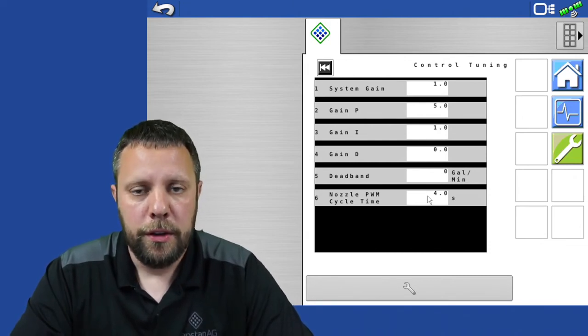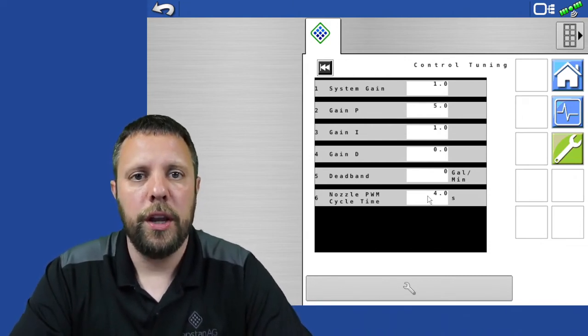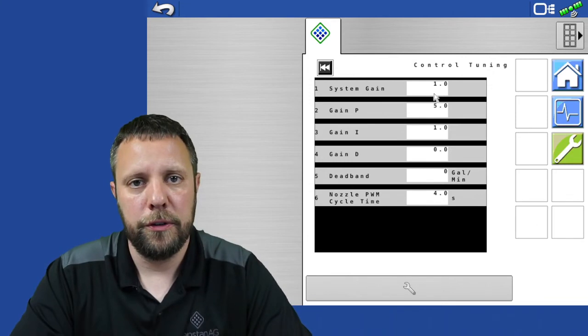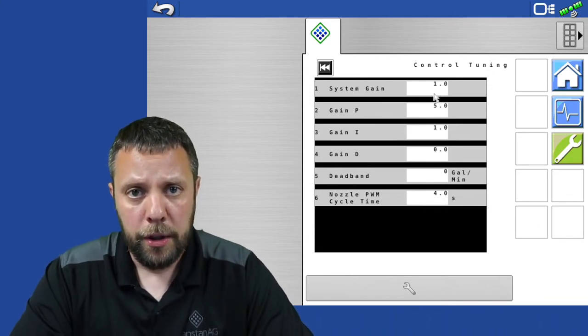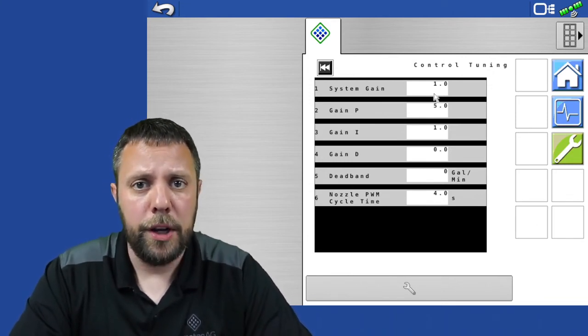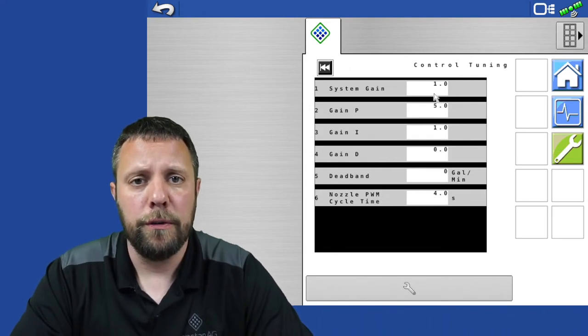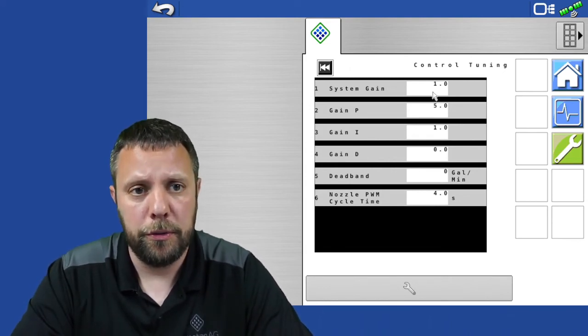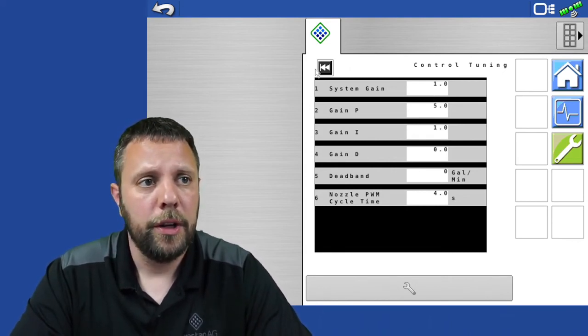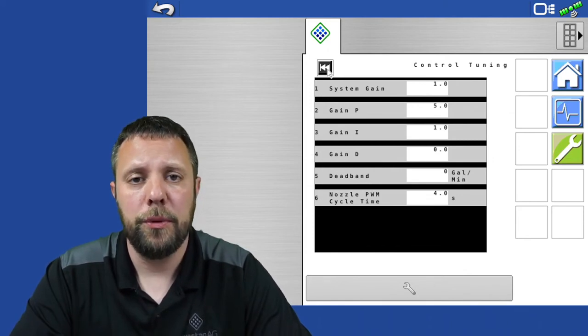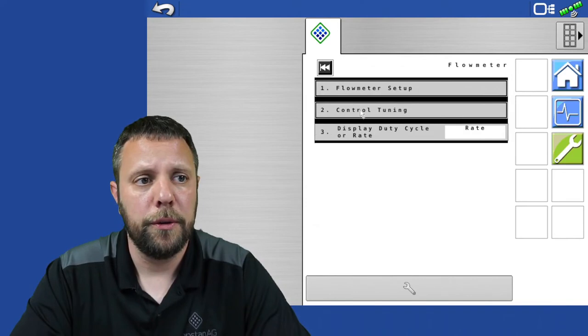If the rate control is slow to get on rate, you can increase the system gain to make it faster. If it is overreacting or overshooting the rate, you can decrease system gain to slow that down. That's typically the only adjustment you would have to consider on the flow control tuning.